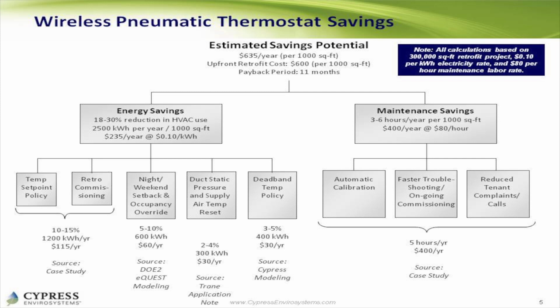So here are some of the savings elements with the wireless pneumatic thermostat: energy savings and maintenance savings. I'm going to cover maintenance savings because it's pretty quick. Because we trend, that is, record all of the temperatures, the set point temperature, actual space temperature, and the branch line pressure, which means the pressure of that control air going up to the damper or the valve, we can now automatically calibrate the thermostat, because those are the three elements you need to calibrate a thermostat. Those old pneumatic thermostats required someone to do it physically at this device itself, so obviously a lot of labor involved. That's a huge maintenance savings.